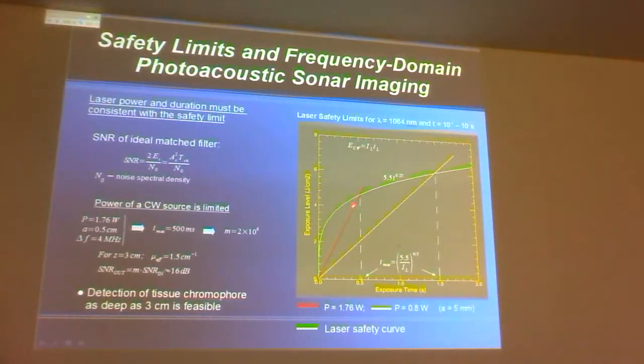And then these are the curves that have been published. So different wavelengths have different time scales, and they have different curves. So for near infrared wavelengths, such as those of the neodymium YAG laser that I presented to you before, you get some of these dependencies, how much the exposure time has to be. So here's the exposure time for a laser whose power is 1.76 watts. This is a CW laser, where you're really looking at the peak power. And here's one for 0.8 watts. So 0.8 watts is a lower power, that means you can expose tissue for a longer time.